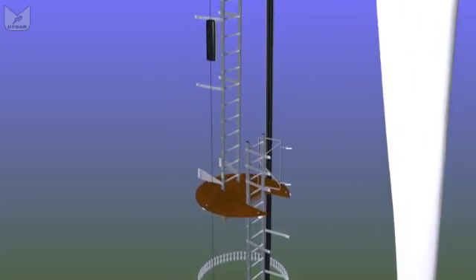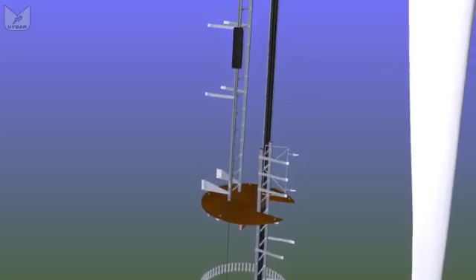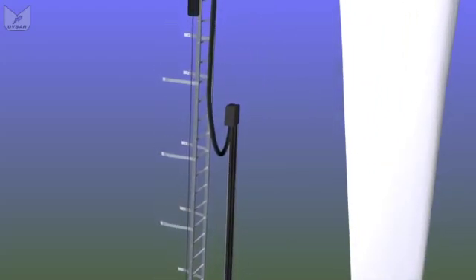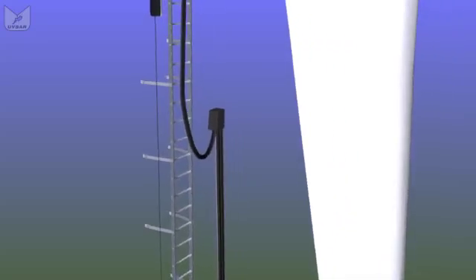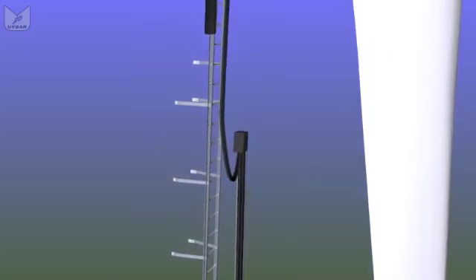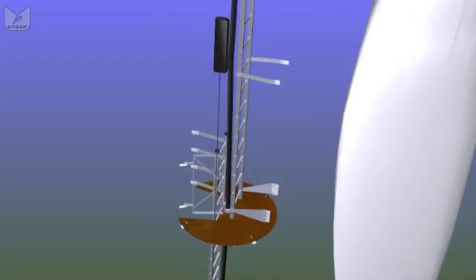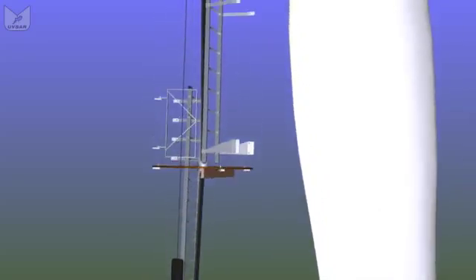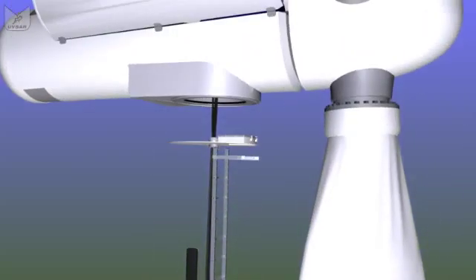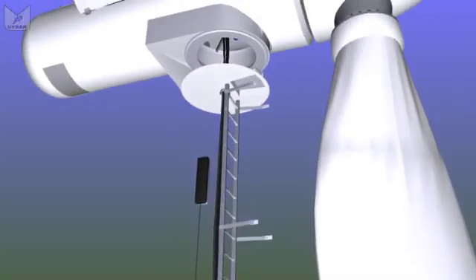But eventually, the main cables stop being attached to the wall, and they hang freely in the centre of the tower, so they can twist as the nacelle rotates to face the wind. If they twist too many times, the nacelle will spin itself around to remove the twists. But as we move up, now the cable goes through a hole in the centre of each platform, and at the top of the tower we have a steel platform with a sealed trapdoor, which we call the yaw platform.